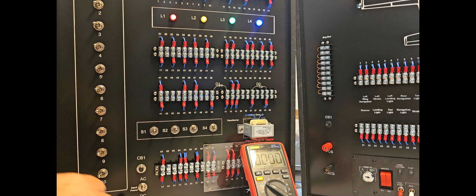A reading is taken using a voltmeter by connecting one side of the meter to a known positive or known negative. For example, if I connect the red lead to the positive battery terminal and leave it there, then every time I touch a terminal with the black lead and get a reading, the terminal can be identified as negative. If I get no reading, I cannot assume it is positive. I must switch the leads around and connect the black lead to a known negative. Now when I touch any terminal and get a reading, I can identify it as positive. Every time I touch a terminal and get a reading, I can identify it as positive or negative.